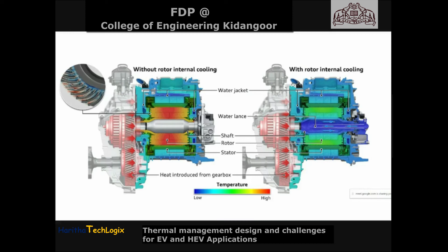But look at this coolant system where thermal management happens with a cooling loop running inside the rotor. It's a hollow rotor design where they circulate coolant inside the rotor, improving motor performance. Compared to the earlier model, the temperature distribution here is much more optimal and acceptable. So the challenge now is to develop the water jacket on the stator part.